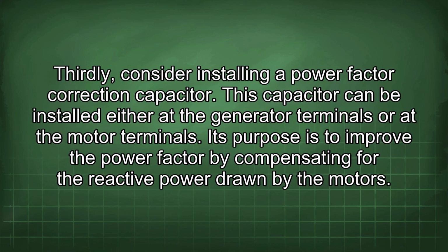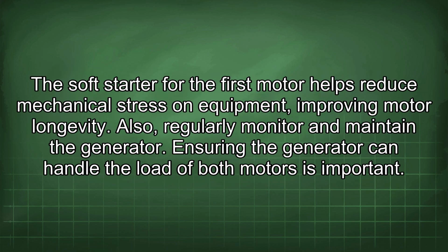Thirdly, consider installing a power factor correction capacitor. This capacitor can be installed either at the generator terminals or at the motor terminals. Its purpose is to improve the power factor by compensating for the reactive power drawn by the motors. The soft starter for the first motor helps reduce mechanical stress on equipment, improving motor longevity. Also, regularly monitor and maintain the generator. Ensuring the generator can handle the load of both motors is important.